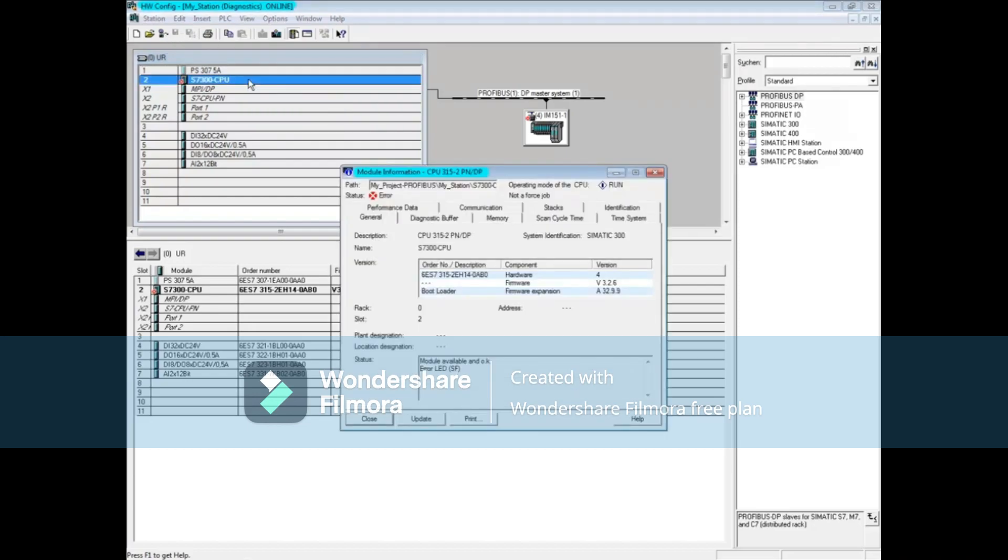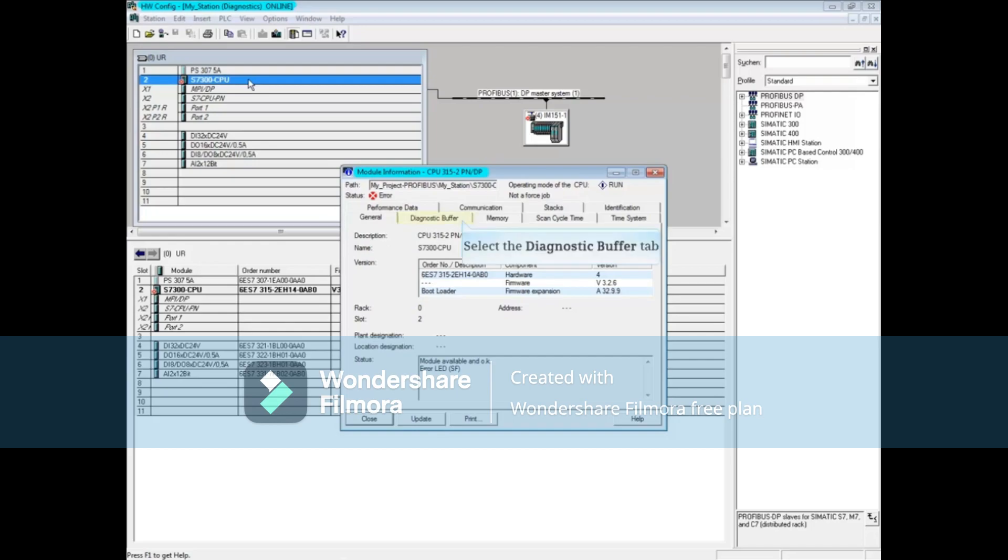Click on the diagnostic buffer tab. The CPU's diagnostic buffer is a good first place to look when faults occur. Sometimes you'll find all the information you need there, other times you'll have to look further.